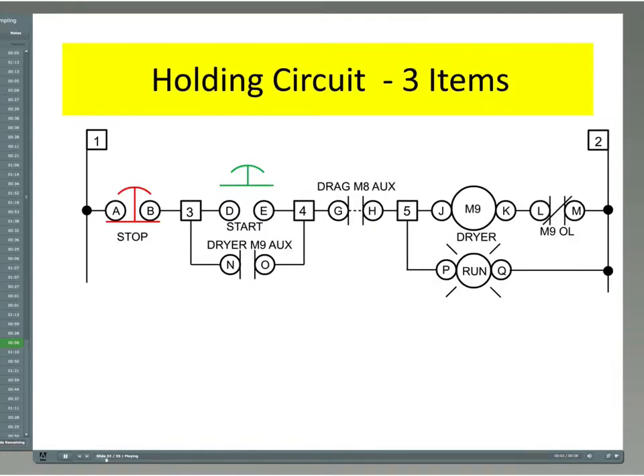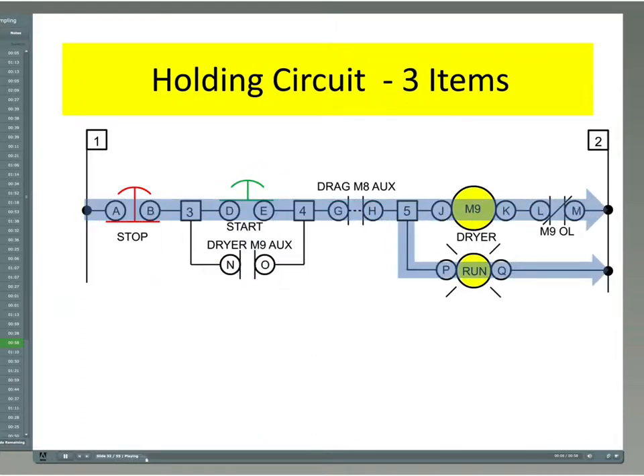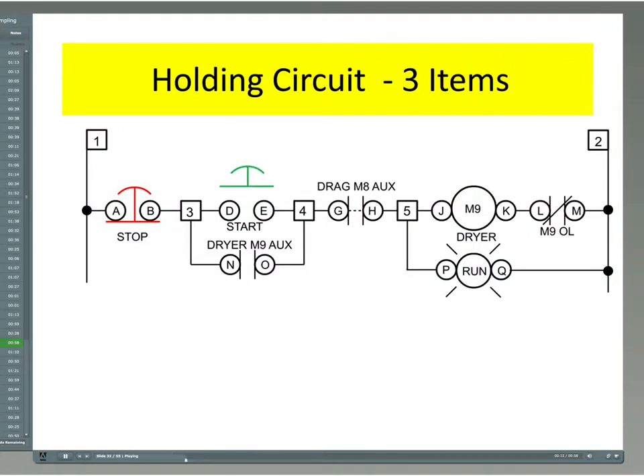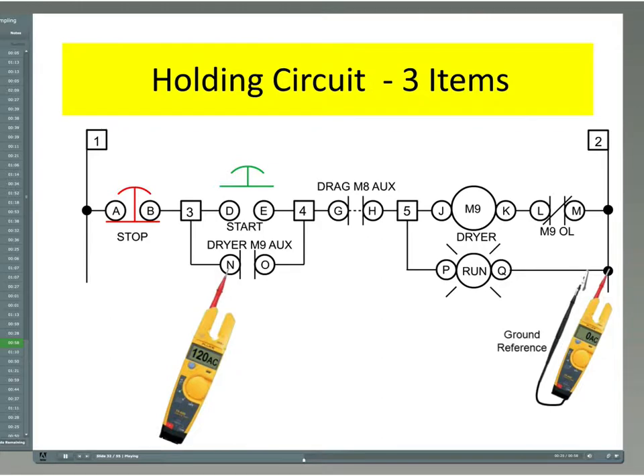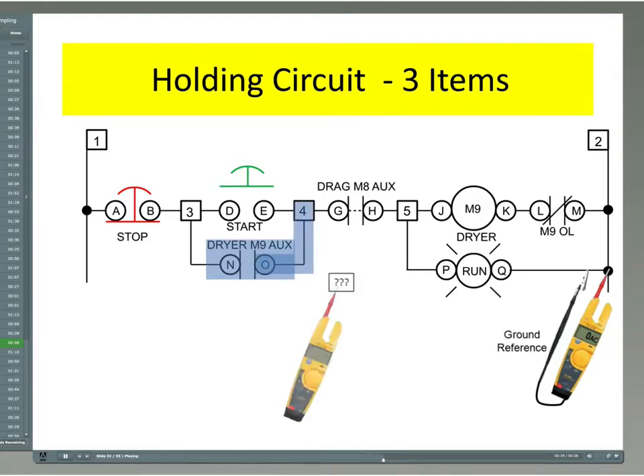One of 3 items is keeping the holding circuit from operating: the connections and wire from terminal 3 to terminal N, the aux contact itself, and the connections and wire from terminal O to terminal 4. One of these can be easily eliminated. The voltage at terminal N should be 120 volts AC whenever the stop switch is not pushed. After confirming 120 volts AC at terminal N, this leaves only the aux contact itself and the connections and wire from terminal O to terminal 4.